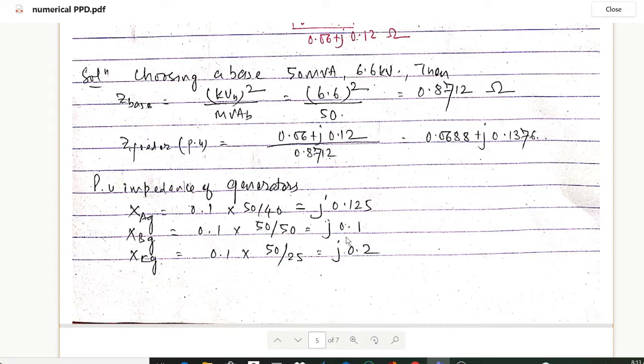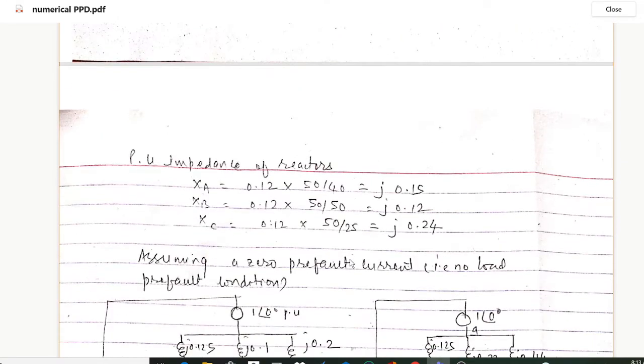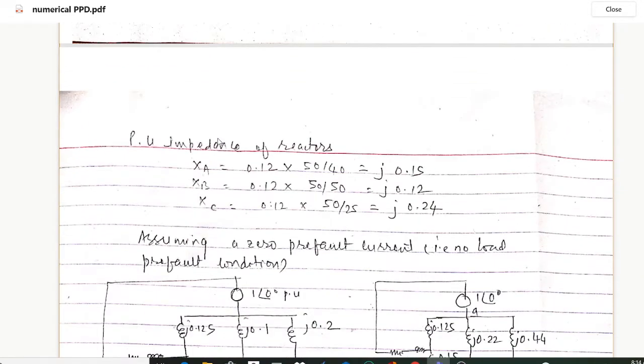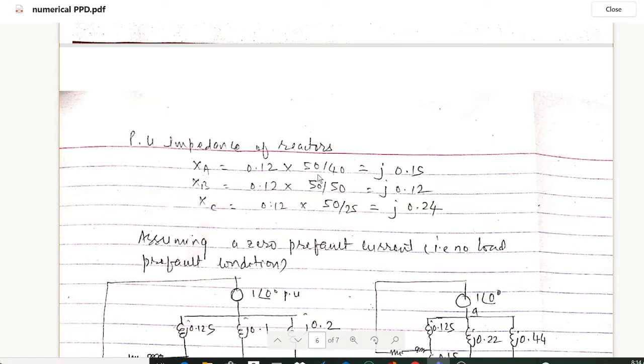For generator C, the per unit impedance is 0.1 × (50/25) = 0.2. For the per unit impedance of the reactors: each reactor is 12%. For reactor A: 0.12 × (50/40) = 0.15. For reactor B: 0.12 × (50/50) = 0.12. For reactor C: 0.12 × (50/25) = 0.24.